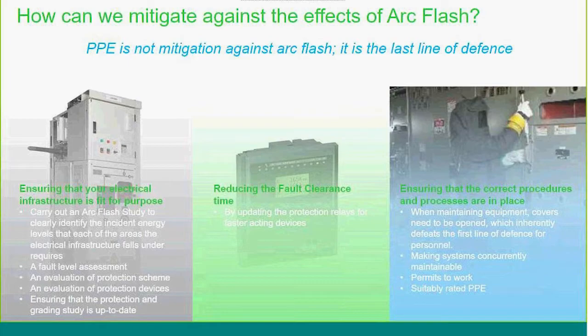And then, clearly, on the procedural side of things, you have a much better understanding of the risk once you've assessed the incident energy levels. So think about how you work with the operatives. Some companies, particularly when it comes to lower parts of the network, insist, regardless of a loss of discrimination, that all their control panels are category 0, or the lowest level of incident energy, which means that, whilst they make their operatives aware of it, they don't have to have any special precautions in resetting devices or operating isolators.